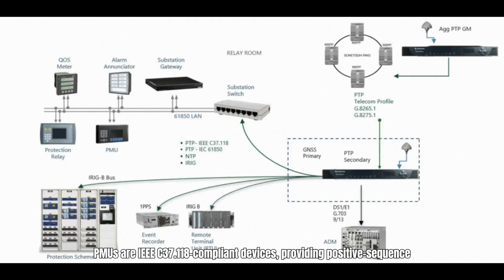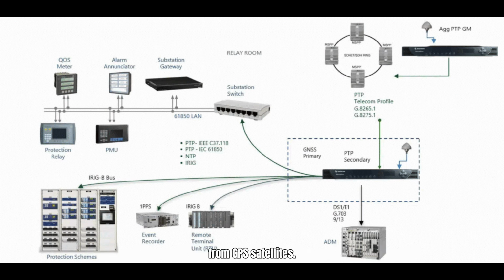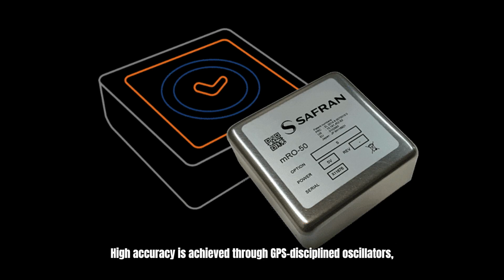PMUs are IEEE C37.118 compliant devices, providing positive sequence phasors with 1 microsecond accuracy timestamps, directly referenced from GPS satellites. High accuracy is achieved through GPS-disciplined oscillators, ensuring microsecond-level time alignment across grids spanning over 1,000 kilometers, with a total vector error less than 1%.